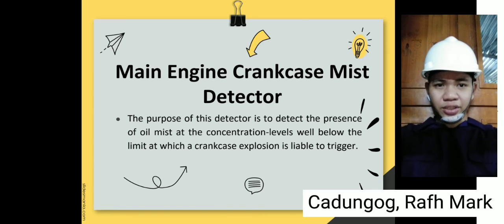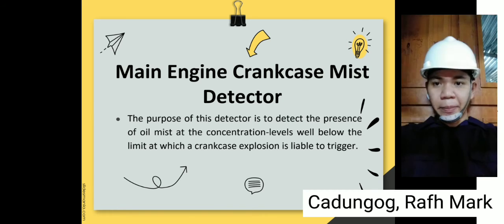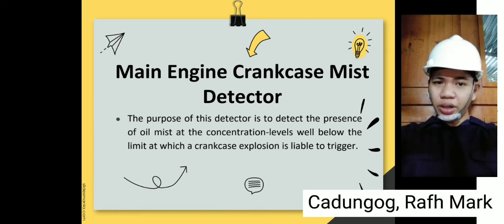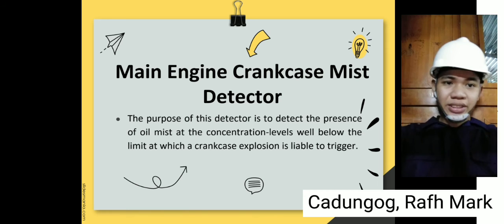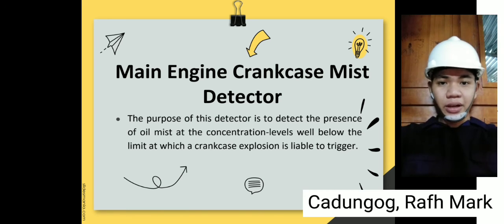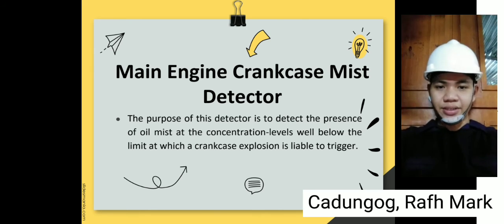The oil mist detector takes continuous samples from the main engine crankcase and checks whether the sample concentrations of mist are well below the level at which a crankcase explosion can take place. The oil mist is drawn into the instrument with the help of a small fan, which takes suction from each crankcase through sampling tubes provided on each crankcase.